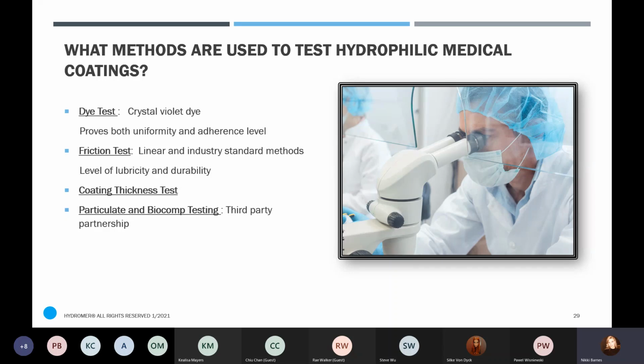The friction test, we have 2 options here at Hydromer. One is a linear test that we created years ago that have worked well for us, and we also have an industry standard method as well. But this obviously tests the lubricity level and shows you those results as well as durability, and I'll get into that a little bit more. We can also offer a coating thickness test, which I think is critical with especially some startups or other new customers that need that reading on when you first coat those, and for some of your testing and how thick our coating is actually on your device to see what changes within that thickness. We've also been working with third parties for particulate and biocomp testing, which we're happy to help you set up.